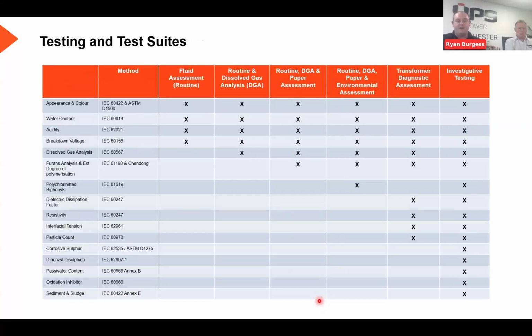So in terms of testing, there are lots of varying tests that can be performed, as you can see from this slide here, and different degrees of suites that can be done. The IEC themselves break down suites of tests into 3 categories. First of all, you have routine testing, and the routine testing is the minimum essential checks that should be performed to ensure good fluid quality. And that is covered in the fluid assessment, or what we call routine. Then you have your complementary tests. These are additional tests that are added to the fluid assessment to give you further information, especially if you're starting to see degradation.